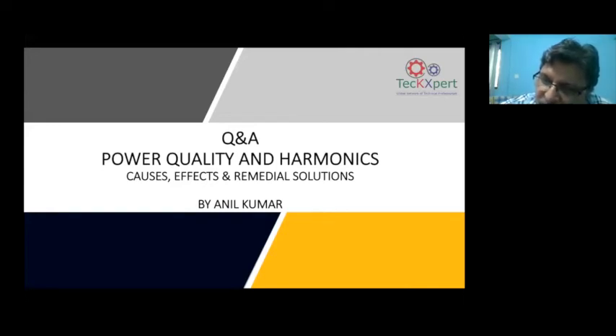But looking at the load in that area, it is only lighting load. Just 2 to 3 motors and lighting load are there. We are not able to understand why the CMD is getting raised to 400 kVA, sir. What is the power factor there? What is the power factor? We are maintaining 0.95, sir.